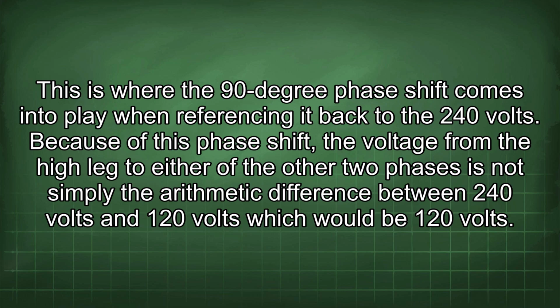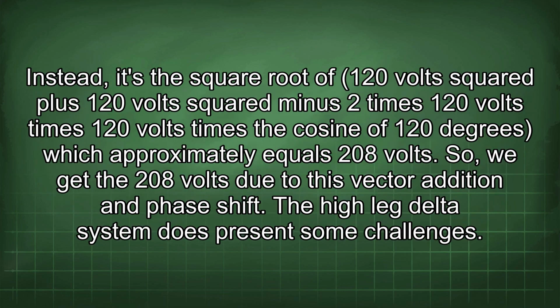Because of this phase shift, the voltage from the high leg to either of the other two phases is not simply the arithmetic difference between 240 volts and 120 volts, which would be 120 volts. Instead, it's the square root of 120 volts squared plus 120 volts squared minus 2 times 120 volts times 120 volts times the cosine of 120 degrees, which approximately equals 208 volts. So, we get the 208 volts due to this vector addition and phase shift.